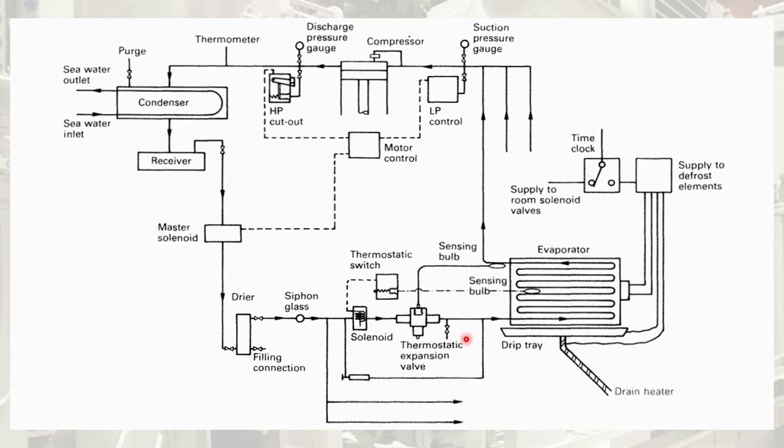For example, if the evaporator is set at minus 4 degrees centigrade and the evaporator reaches the set point, then the sensing bulb attached at the outside of the evaporator sends a signal to the thermostatic expansion valve to reduce the pressure drop and completely block the flow of refrigerant to the evaporator. In parallel, it also sends a signal to the thermostatic switch, which sends a signal to the solenoid valve to close and stop refrigerant flow. Even when the solenoid valve is closed, refrigerant present inside the evaporator coils up to the suction valve is still taken on suction by the compressor, pressurizing the discharge side.